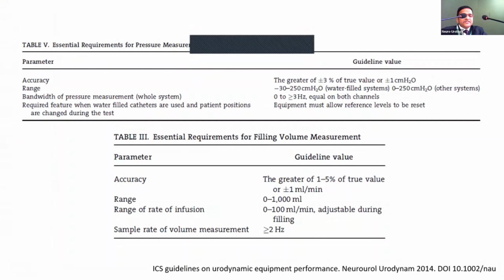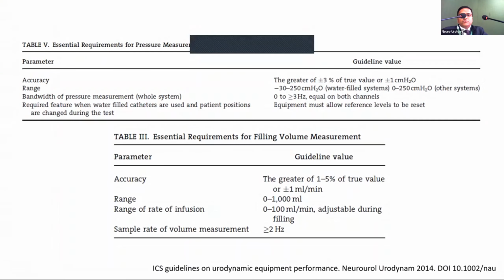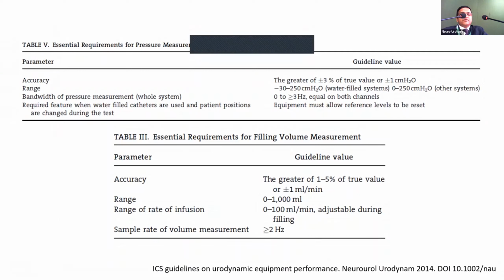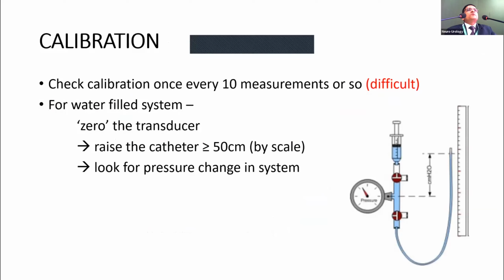So for accuracy, ICS has given good guidelines. The pressure should be within 1 centimeter accuracy, or 3% of the measured value, whichever is more accurate. The ranges are written, and the sample rate of volume measurement should be 2 hertz or more. I don't have to cram it up because these are available on the ICS website. For calibration, these imported machines have automated calibration, but at times it's good to keep checking. For the water-based system, it's very easy. You just take the water column up by 50 centimeters and see what your machine is showing. That would tell you whether it's well calibrated or not.